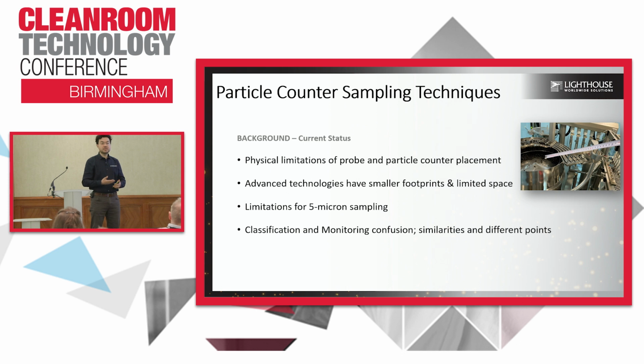And of course, there's a limitation with 5 micron, which also led in 2015 to the revision of ISO 14644 Part 1, cleanroom classification, especially for the pharma industry. 5 micron is no longer available for ISO class 5. The reason is easy, because it's not always easy to collect these 5 microns throughout this tubing while you have 29 particles per meter cube. And we always need the shortest time period to get the fastest action possible. So if you lower it down to per minute, you have to find either 1 or 0 particles at 5 micron, which is almost impossible with the tubing system, and there's a technology barrier behind it.